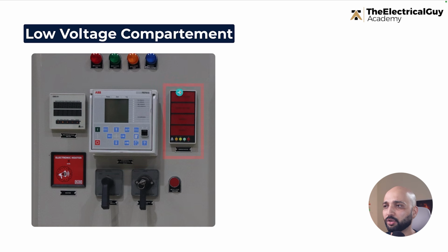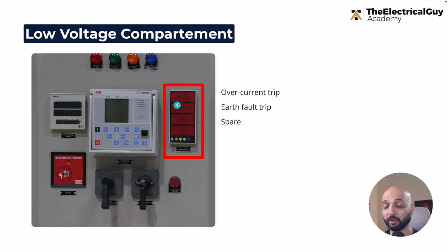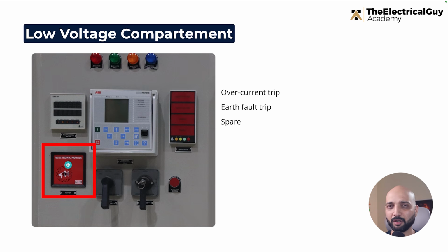Then we have an annunciator here. Now for this particular panel, they have provided overcurrent trip indication, earth fault trip indication, and then there are 2 windows as spare. So if I'm the customer, I can choose and decide what indication I want there, and I can wire things accordingly, right? And with that, we also have an electronic hooter, which will make noise in case something goes wrong.